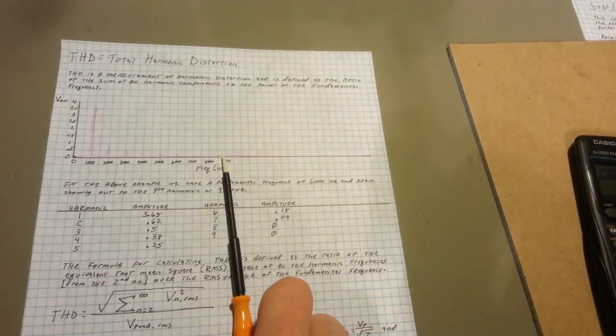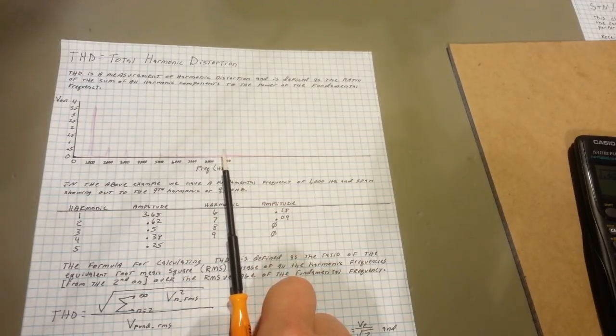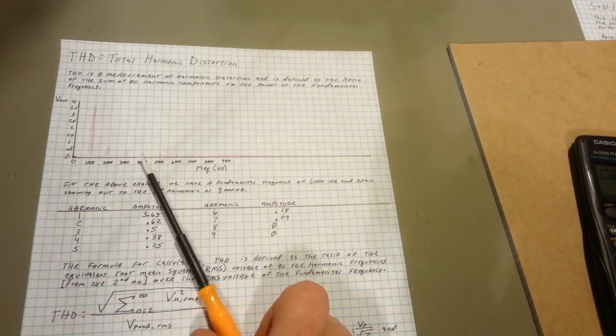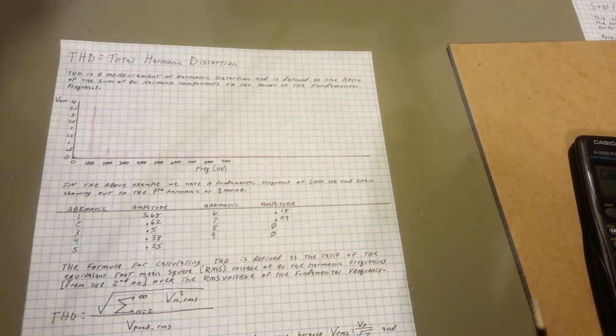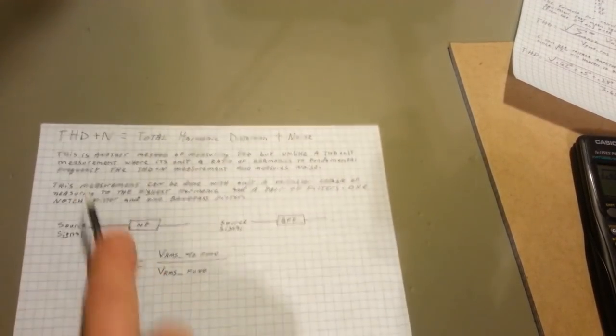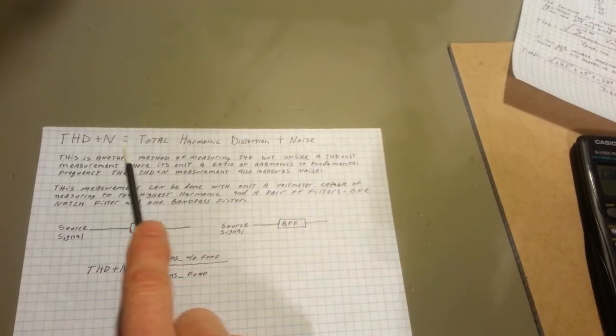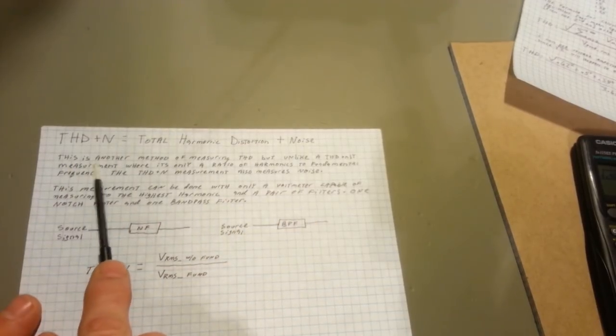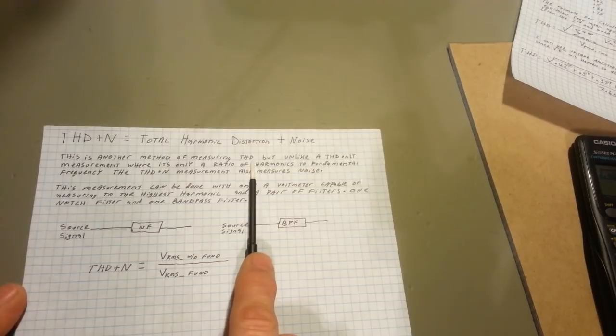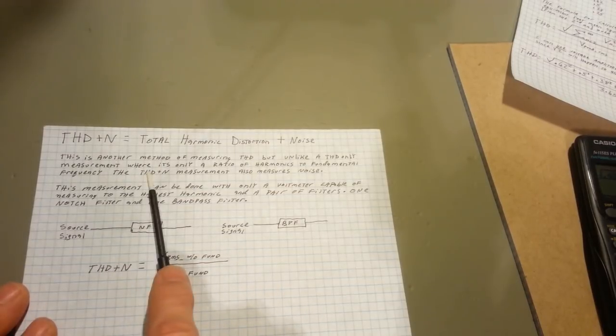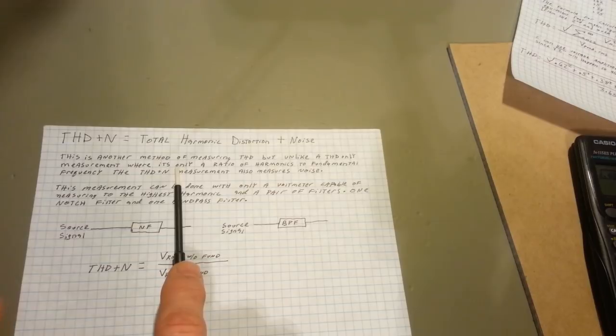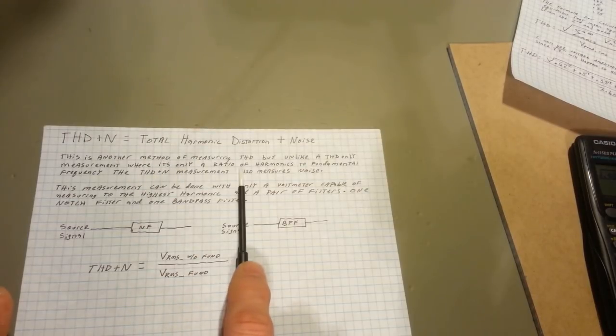And I can, again, on the communications test set, once I get that fired up, I can show THD measurements, and actually the next one we're going to do is THD plus noise measurements. So actually the last one we're going to talk about is going to be THD plus noise, or total harmonic distortion plus noise. This is another method of measuring THD, but unlike the THD only measurement, where it's only a ratio of harmonics to fundamental frequency, the THD plus noise measurement also measures noise.